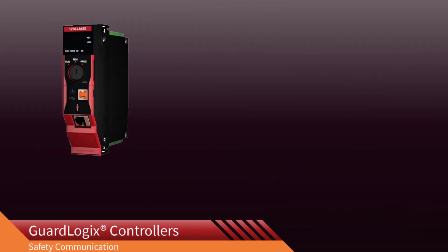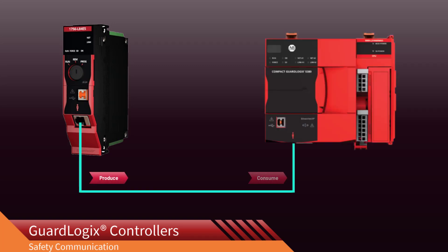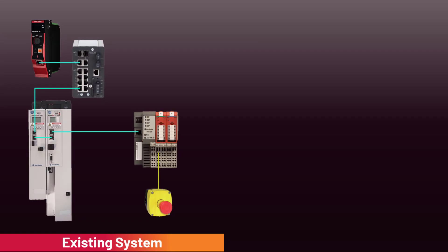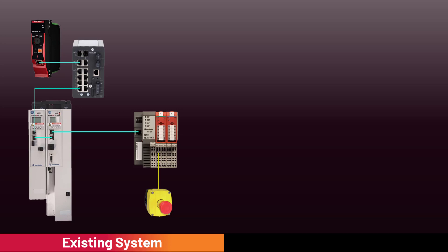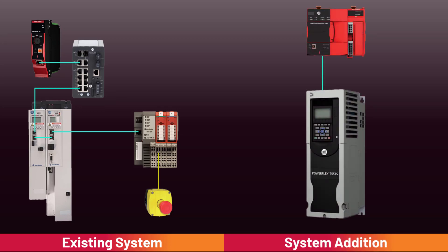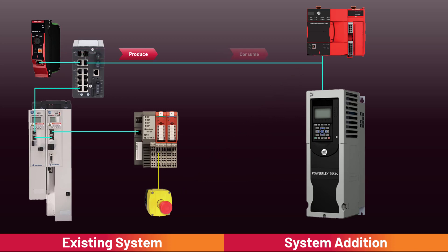Safety data from one GuardLogix controller can be sent to another GuardLogix controller using a produce and consume CIP safety network connection. This video will show the steps to set up and configure a safety produce and consume connection. In this example, a GuardLogix system with an emergency stop input exists on a machine, and a new machine section with a Compact GuardLogix and a PowerFlex 755 drive are going to be added. The new system is required to monitor and react to the existing emergency stop push button. A simple way to share safety data between controllers is to produce and consume safety tags.